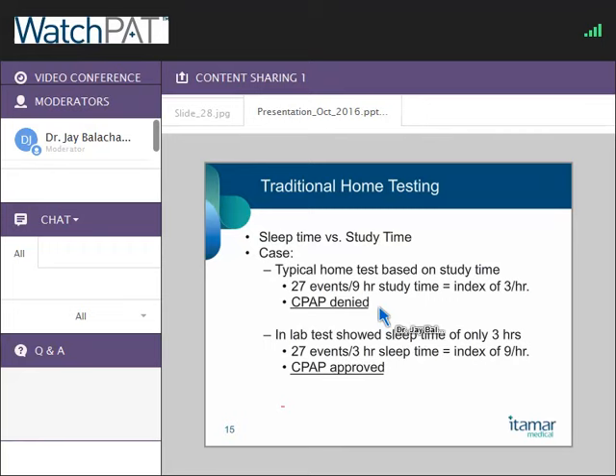There's a question that just came through asking if any manual scoring is needed. I've personally found that I haven't needed to do any manual scoring — I'll inspect the raw data to make sure non-valid data is appropriately marked. But having worked with several different Type 3 devices like the Nomad, the ResMed Apnea Link, and the Alice Night One, I find that I have to pay attention to non-valid data a lot less. The WatchPAT is better at denoting non-valid data than those other devices. I personally have not needed to do any manual scoring.